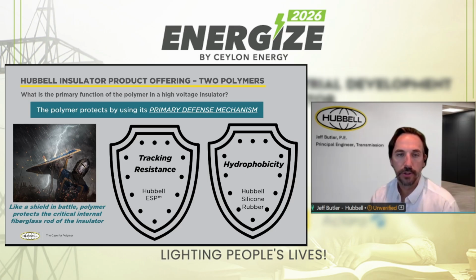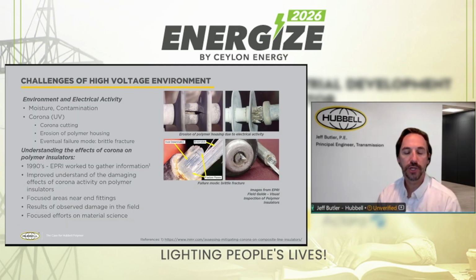So when we're looking at polymer insulators, it is understood that there are challenges that are faced in the electrical environment. There's moisture, there's contamination, there's corona activity, electrical activity, which creates UV. There's also UV from the sun, from solar exposure. So all of that can lead to the phenomenon of corona cutting, erosion of the polymer housing, and an eventual failure mode referred to as brittle fracture. That's what the picture in the bottom left shows, brittle fracture, where you see fiberglass strands that have been cut clean. It almost looks like they were cut with a knife, and then the remaining strands lack the mechanical strength to maintain the mechanical load. As I mentioned, the primary function of an insulator is carrying that mechanical load.